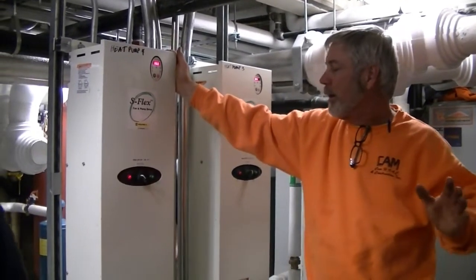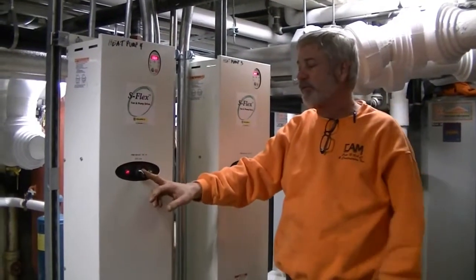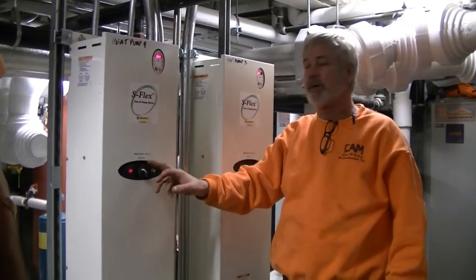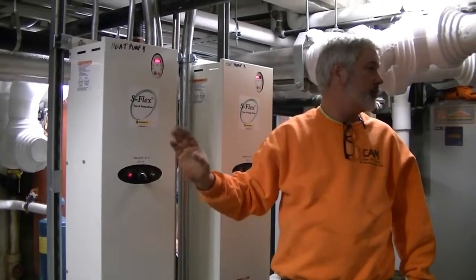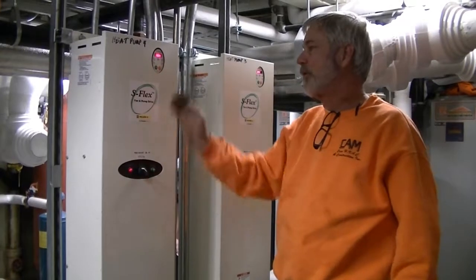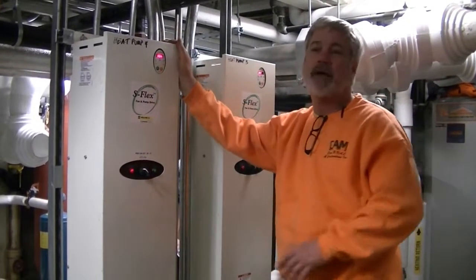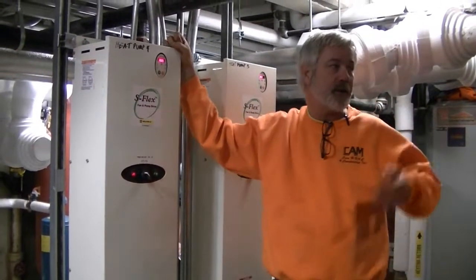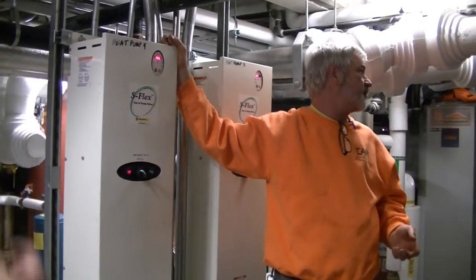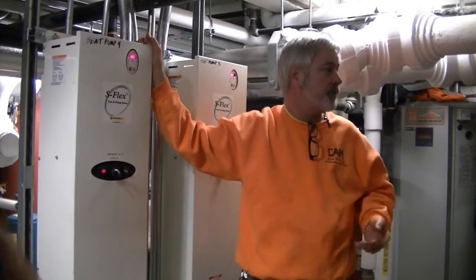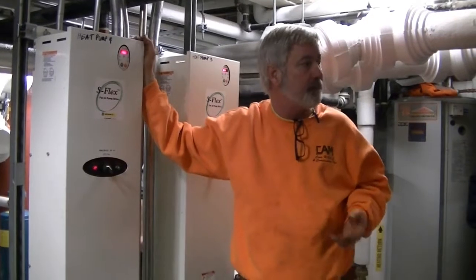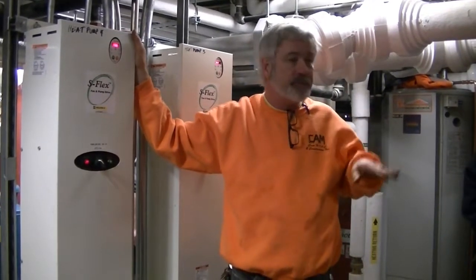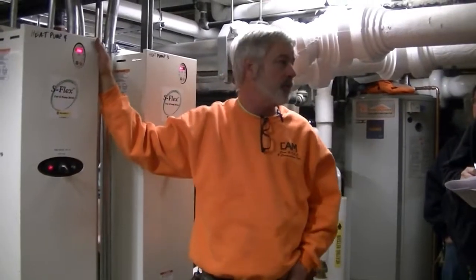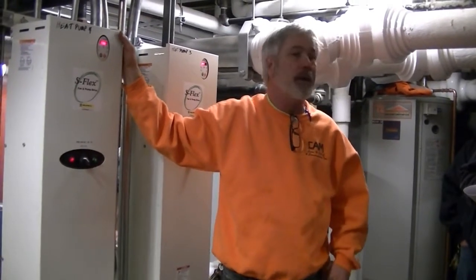Okay, you do have your inverter and bypass switch here, so you can run it on the inverter. If the inverter crashes, you can bypass it. But again, like I said, you've got to be careful what you're doing when you're running a bypass. You've got to know what the rest of the building systems are doing at that time, and just keep an eye. You don't want to blow a pump up because you hit the switch and walk away.